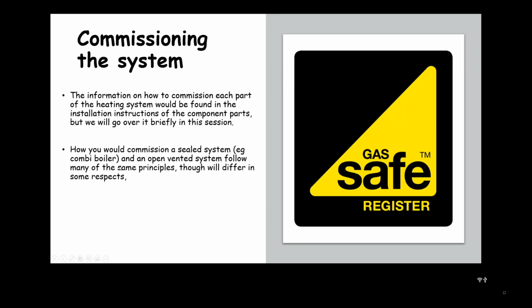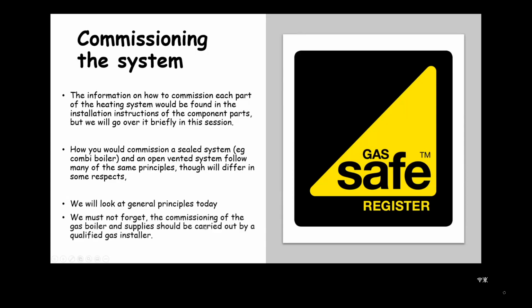So how you commission a sealed system like a combi boiler and an open vent system has a lot of the same principles essentially. They might differ in some respects, but we're going to look at the general principles today. Obviously, if you're commissioning a gas boiler and the gas supplies, you should make sure that only a qualified gas installer does that part of the commissioning process.